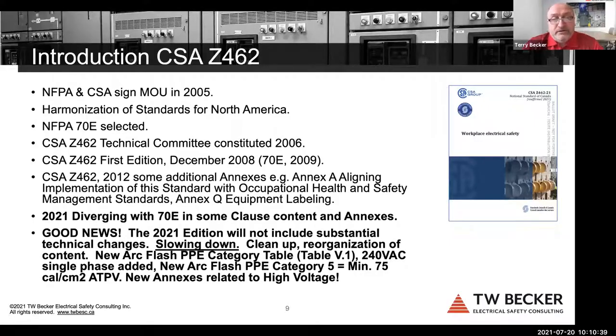So again, Z462, 5 editions, significant changes. This time around, we added some new annexes that are not in 70E. NFPA added an annex on capacitors that we don't have in Z462, right? So the annexes are where there's a real difference, a significant difference in, quote, the technical content. And in my opinion, if you had 70E and Z462 and used both, you'd have the best of both standards, with this divergence that's occurred in the annexes specifically.